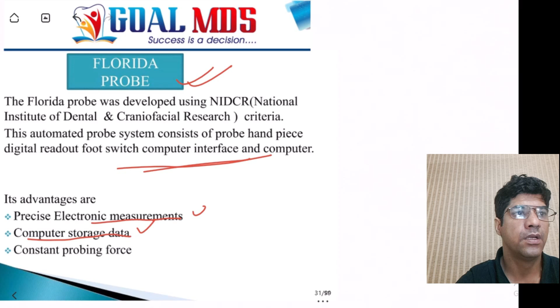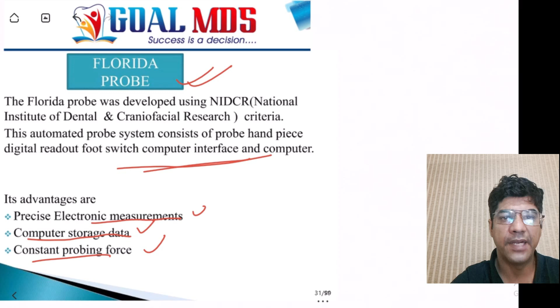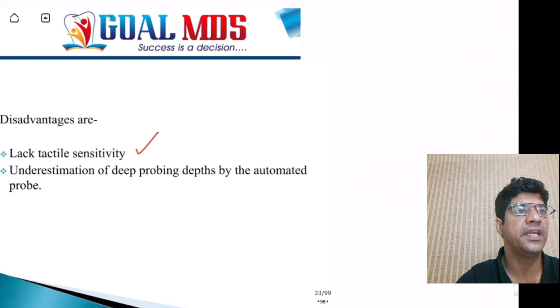So what are the advantages? It gives a precise electronic measurement, and the data is stored on the computer, with constant probing force. It is basically used for measuring the pocket depth. It has the ability to create digital periodontal charts. It is accurate, and it also maintains a constant probing force. That gives uniform and accurate results. The constant force improves the reliability and reproducibility of the measurement. Disadvantages: lack of tactile sensitivity. So these are the disadvantages.